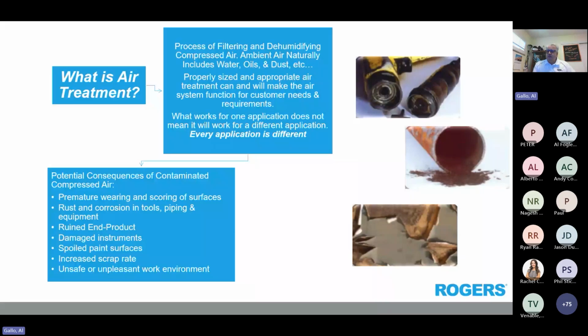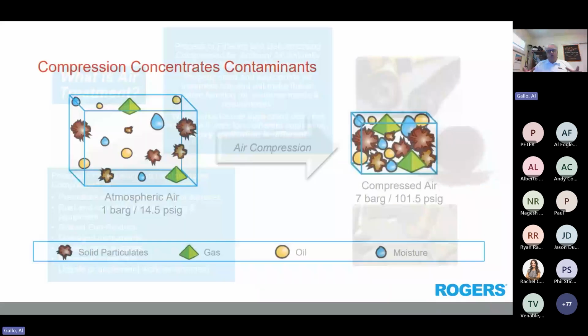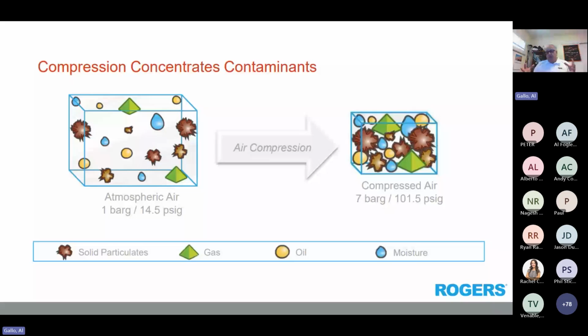We want to make sure that we put in the appropriate treatment, and we only dry the air to your application. On a previous webinar, I went through the selection of what type of air treatment is appropriate for what types of applications, so please refer back to that. It was a couple months ago. But again, to reiterate, when we compress air, we take 7 gulps of air and compress it down into 1 gulp. We're basically concentrating the contaminants in the compressed air stream, so we need our filters and dryers and air receivers to help filter some of that out.